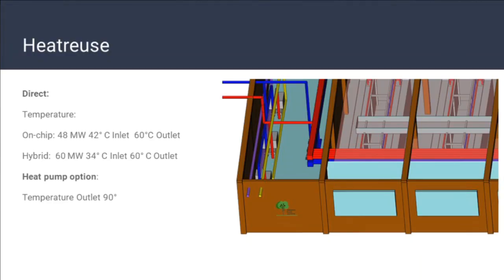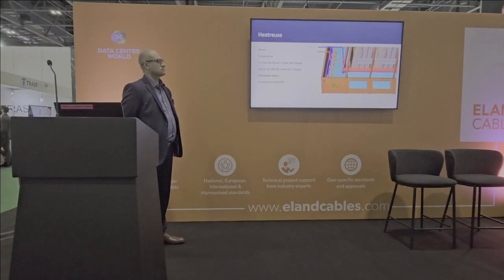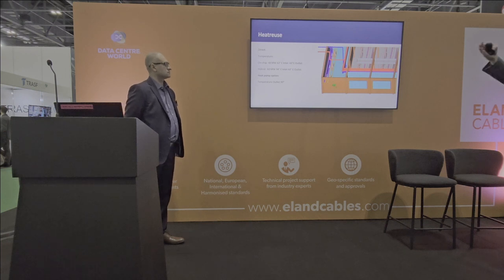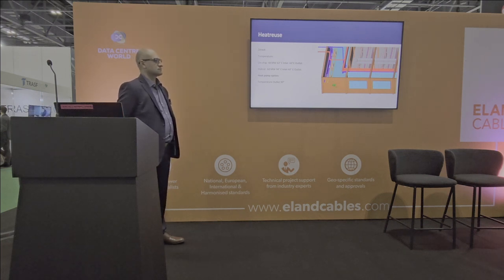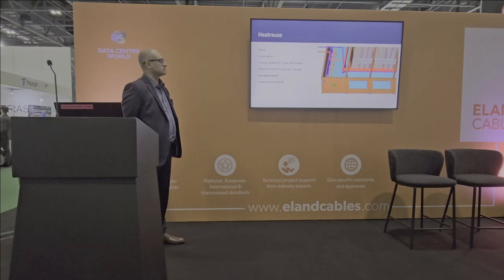We hear a lot today about heat reuse, and with liquid cooling, David and I look at a lot of liquid cooling cases, and we actually try to push the envelope by going higher in temperatures. We have found a relatively moderate configuration, but if we go with an on-chip scenario or the hybrid scenario, we are enabling a direct output of 60 degrees temperature, and if we add heat pumps into this setup, we can easily go to nearly any heat grid up to 90 degrees.